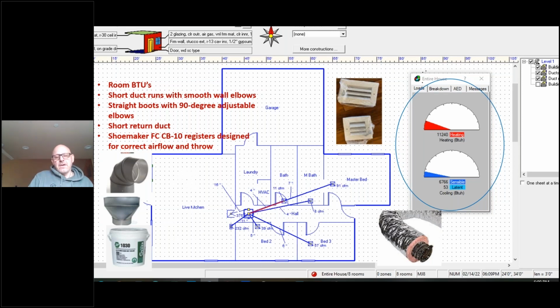The supply or the return. So the difference in temperature between the return and the supply has to be really less than 25 degrees. If you have a gas furnace with 130-degree air coming out of it, and your air is 75 degrees coming in, your delta T is going to be 80, I think, 50. Anyway, it's above 25. So that air is just going to want to sit in the ceiling. There's nothing you can do. There is no entrainment. It just wants to sit. This is a hot air balloon effect.